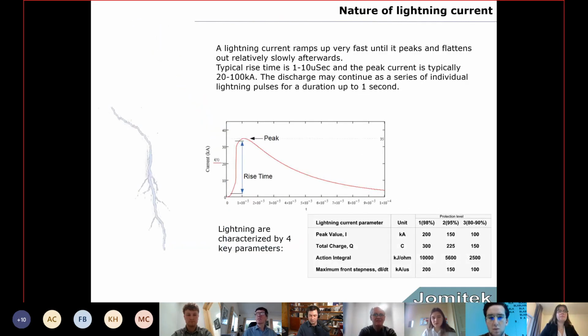If we look at the nature of lightning currents, we have a current that rises up pretty fast, roughly 1 to 10 microseconds in rise time, with a peak current that could easily be more than 200 kiloamps or more. So it's quite dramatic what happens here.